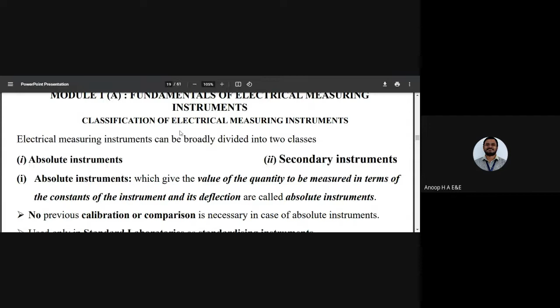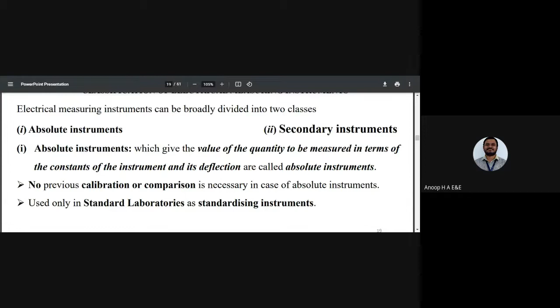So once we have this broad classification, I'll be having the absolute instruments, which will give the quantity which is to be measured. I call it the quantity to be measured in terms of the constants of the instrument, so I call that an absolute instrument. No previous calibration or comparison is required. It is generally used in standard laboratories and as standard measuring instruments.